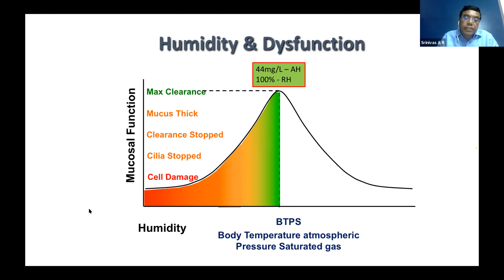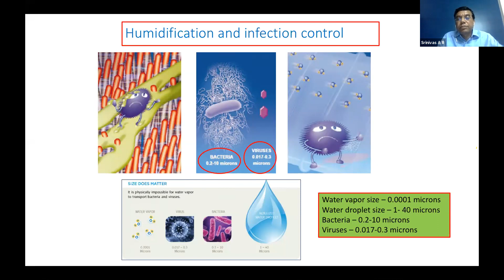So how does it prevent infection? If you look at the size of the water vapor, it is very tiny. That's only 0.0001 microns. A virus is about 1 to 40 microns. A bacteria is about 0.2 to 10 microns. And a water droplet is much larger. So a water droplet can carry both virus and bacteria, whereas water vapor cannot carry virus or bacteria. Therefore, humidified air will not generally carry any virus or bacteria along with it, unless the bacteria transfers through the side of the tubings. So it prevents infection significantly.